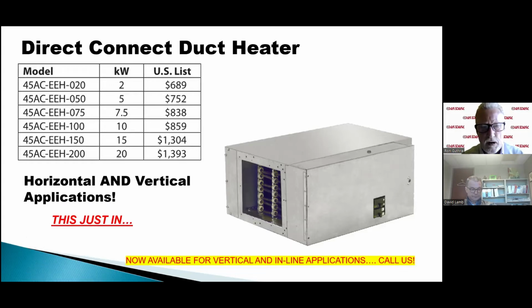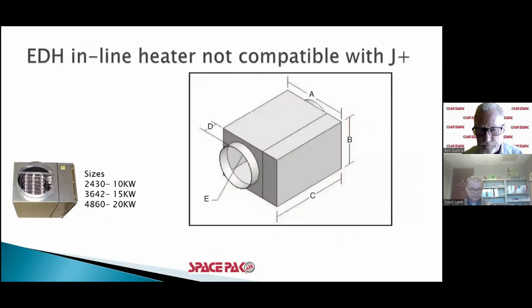All right. There's another point I want to make, and this is the EDH model. Okay, this was an inline model. You can see in that drawing there that there's a 9-inch round collar on both sides, inlet and outlet. This is not compatible with the J series units for board versions 1 to 3. Okay. And well, I can go back and show you. I don't think I have another picture of the board coming up, but there was a signal that the J series board, not the J plus, gave when the fan was running. It's some kind of DC voltage signal, so it wasn't a matter of just adapting that with a relay. That signal was for airflow.